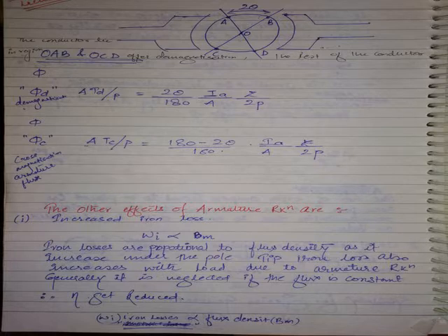Apart from that, under the pole shoe and between the armature core, the air gap is not so ideally uniform. There is 1 mm air gap only, but if you think ideally, that 1 mm is not so smooth. Why? Because on the armature, what are they? Slots. In that, conductors are there. So, the flux distribution in the air gap is not so smooth, so you will be having some variations. Those variations may again cause some eddy currents by linking. That's why the pole shoe is more sensitive, particularly when it comes to iron loss, as well as the pole core, as well as the yoke, everything should be laminated.